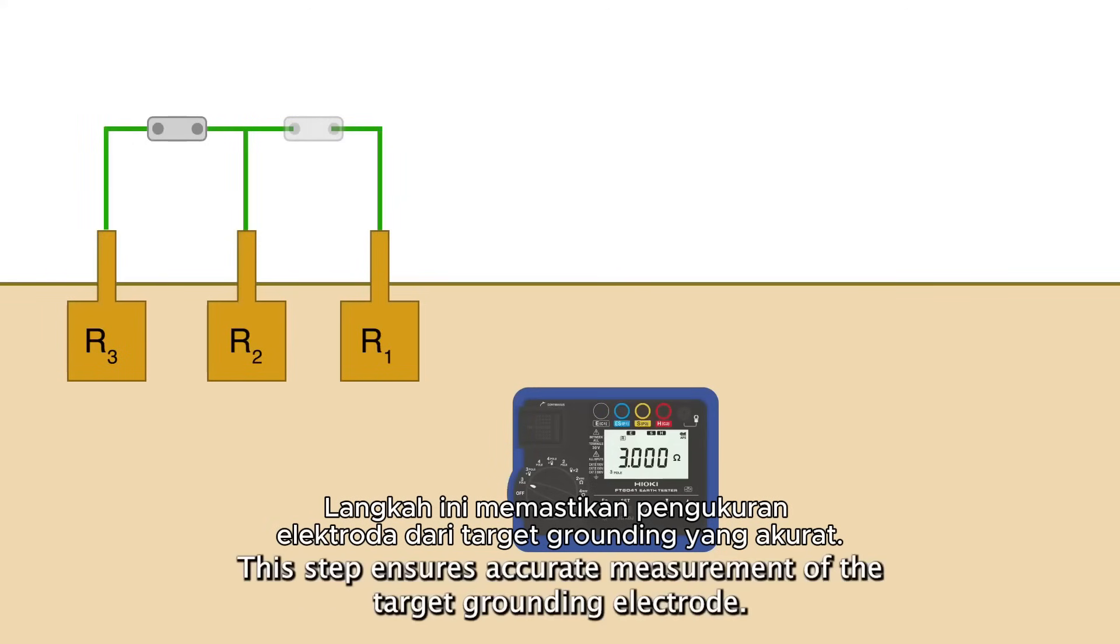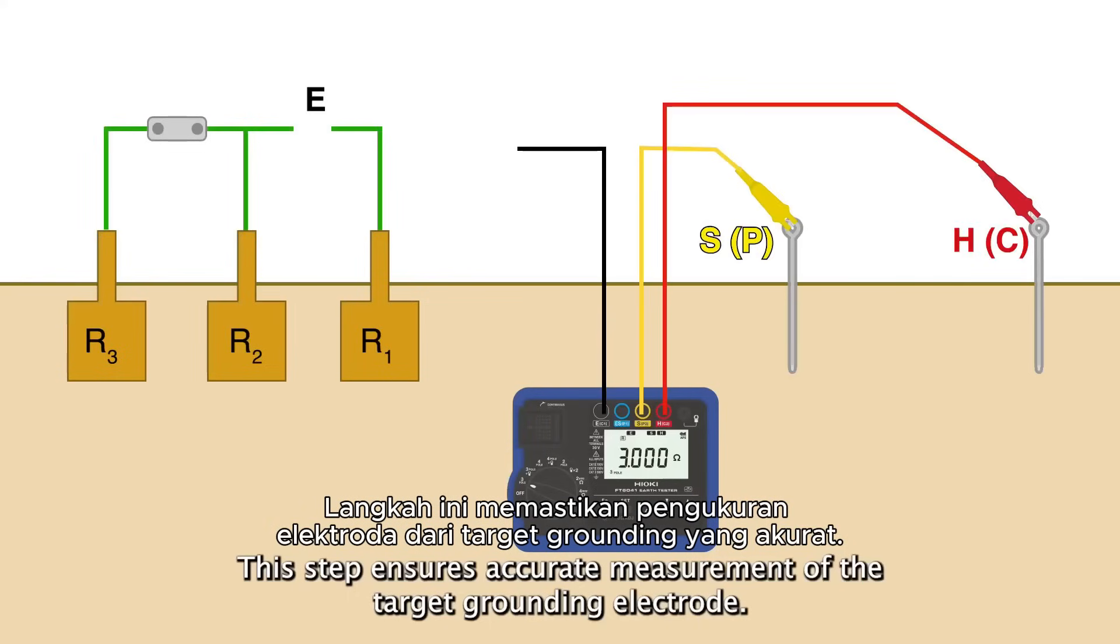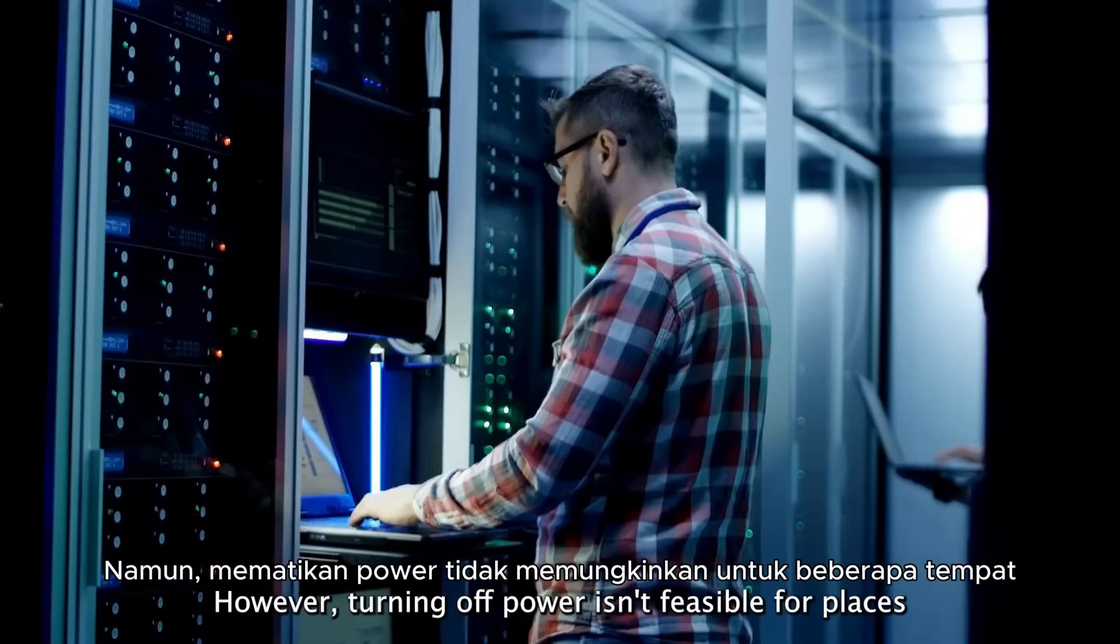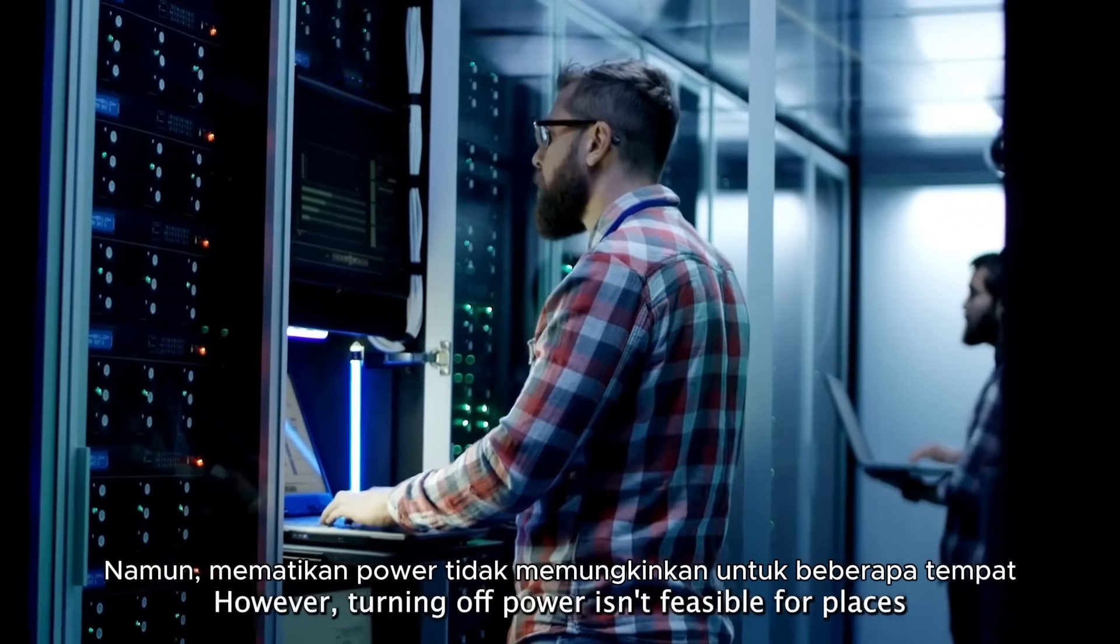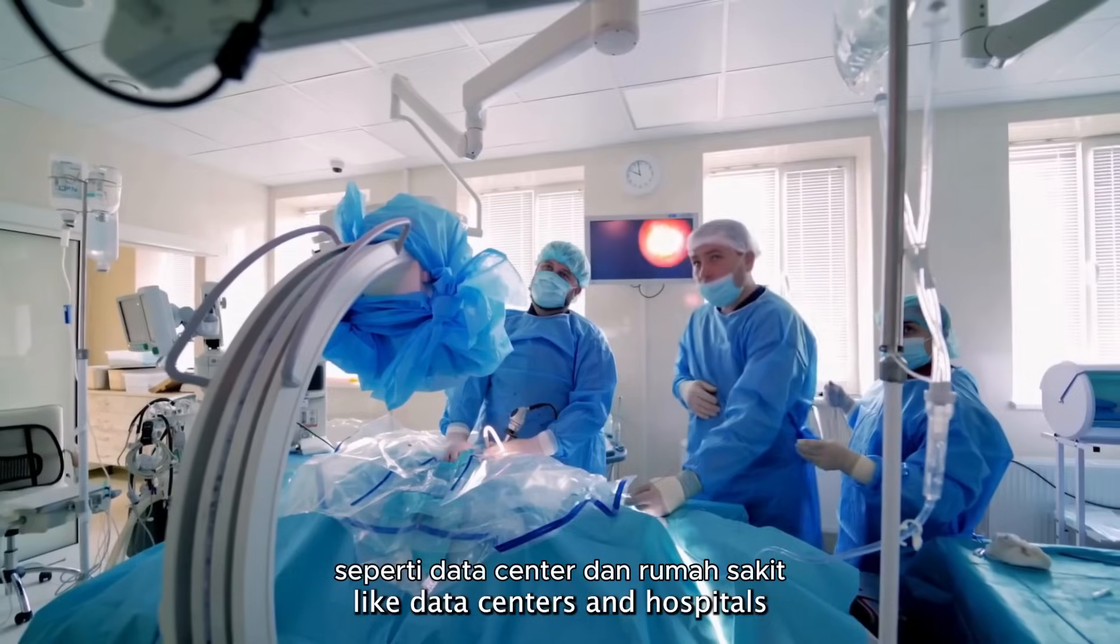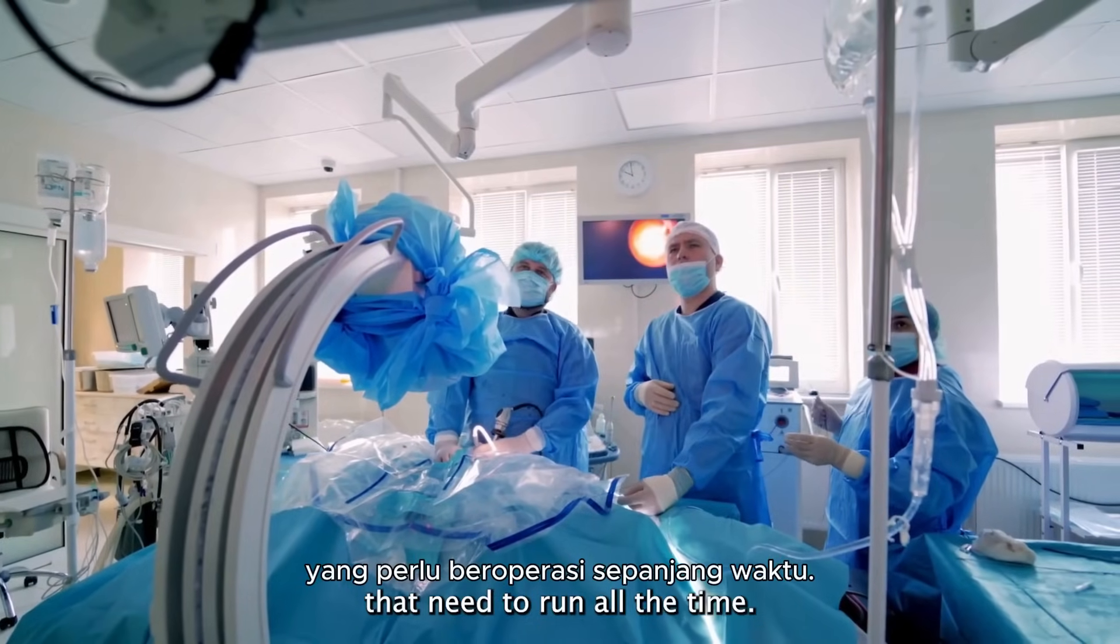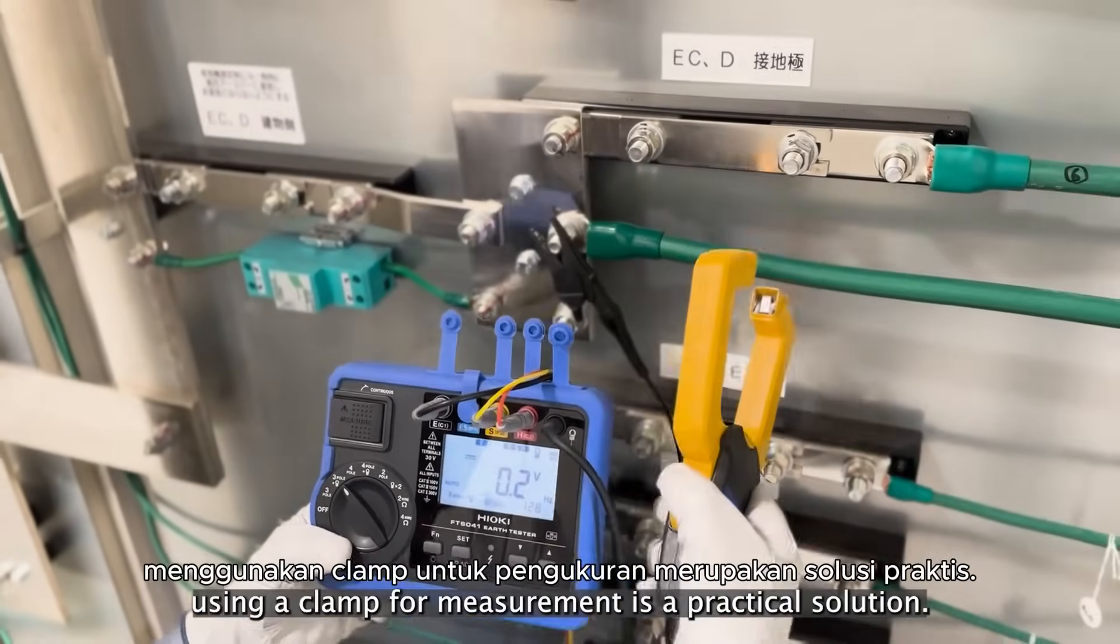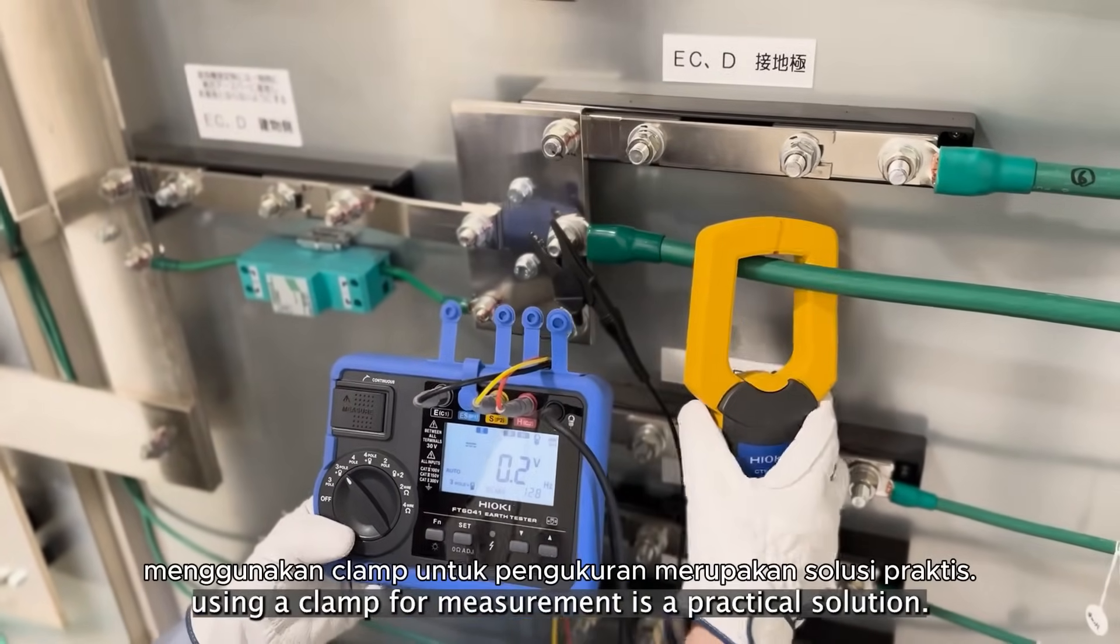This step ensures accurate measurement of the target grounding electrode. However, turning off power isn't feasible for places like data centers and hospitals that need to run all the time. For these situations, using a clamp for measurement is a practical solution.